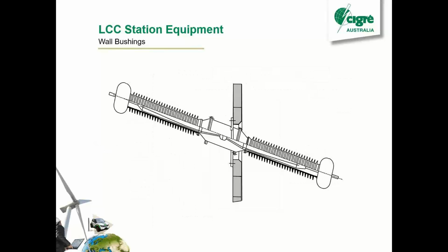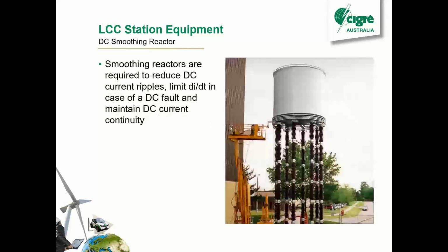It's a picture of a wall bushing. Yeah, we need quite a lot of bushings in HVDC to get into the converter hall and get out again. This is a smoothing reactor. Again, this would be no good in New Zealand. You can see it looks like it would fall over quite easily, but yeah, they're required on the DC side to reduce your current ripple, limit the rate of rise of the current. It's to help your thyristors and to maintain your DC current continuity when you get down to those low power levels.